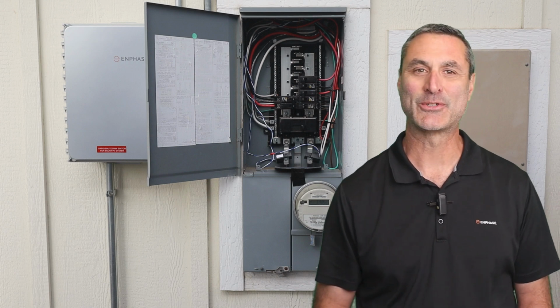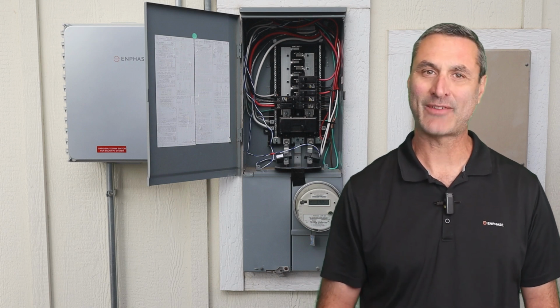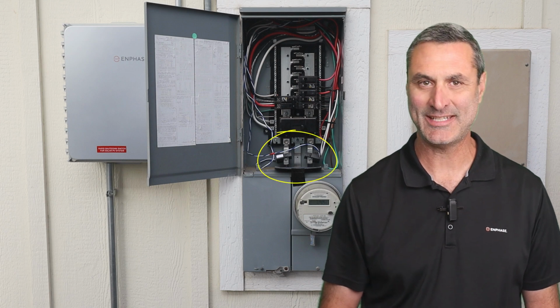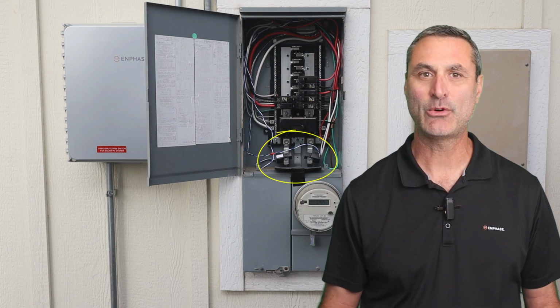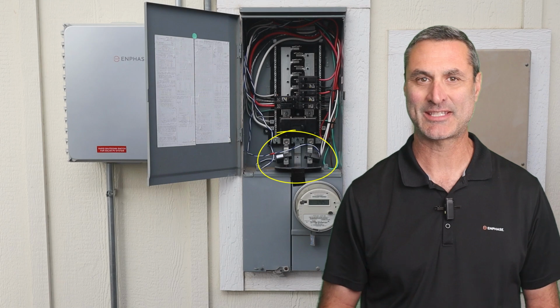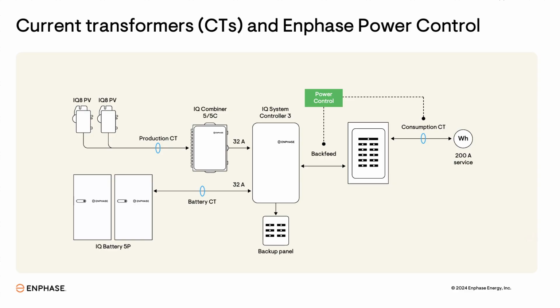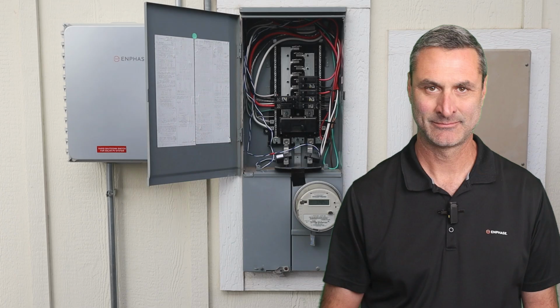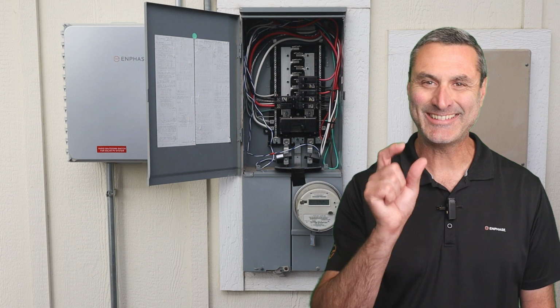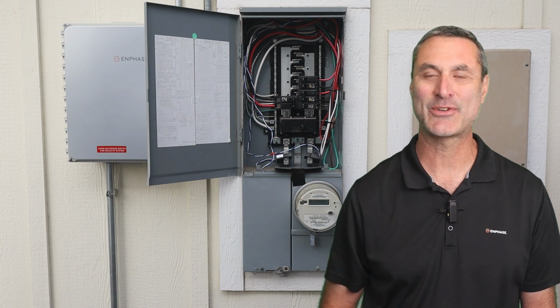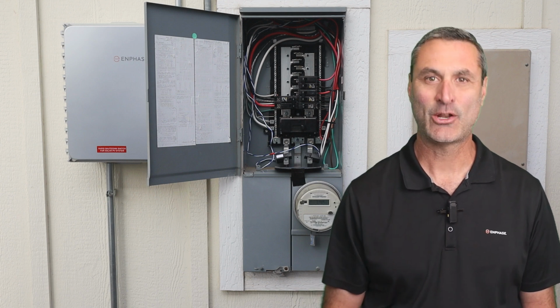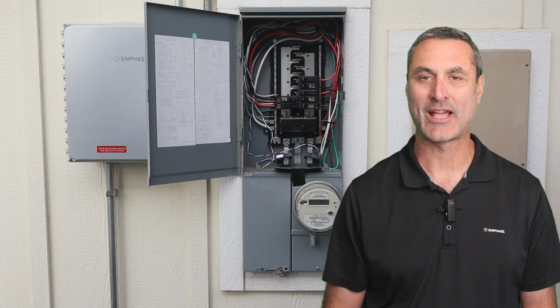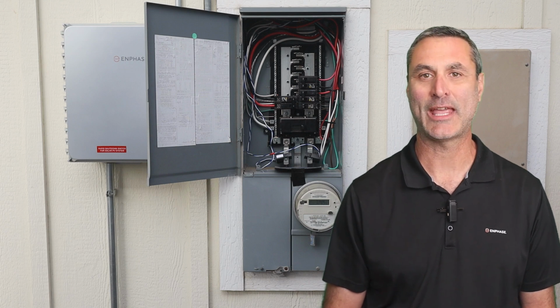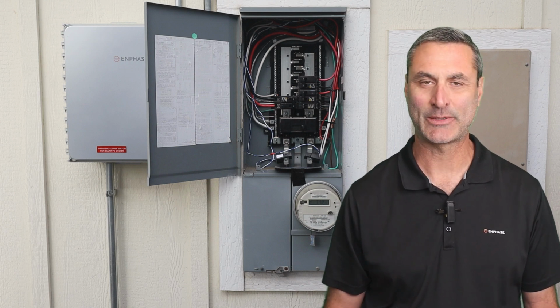Here's how Enphase Power Control works. It uses little devices called current transformers, or CTs for short, to measure the flow of electricity through an Enphase Energy system. They measure electricity imported from the electric grid, produced by the solar PV system, and discharged by the battery. You can think of CTs like tiny little energy accountants, keeping track of every single watt. And all that data gets sent to what we call the brains of the operation, and that is the IQ Gateway. And this is where the magic really happens.